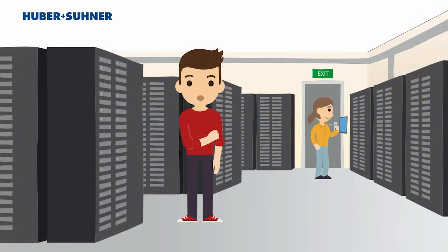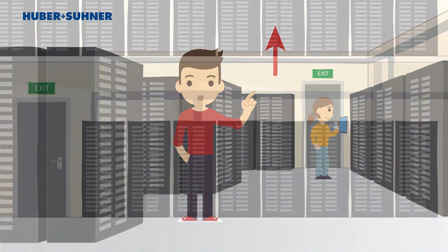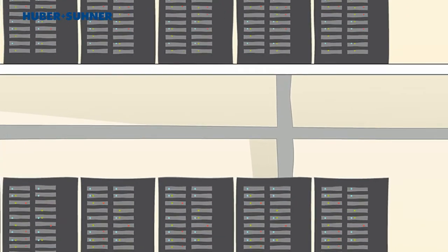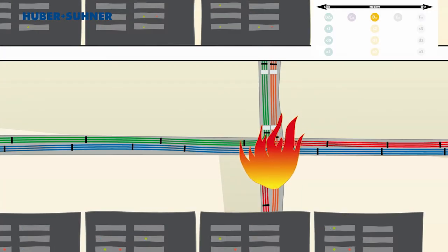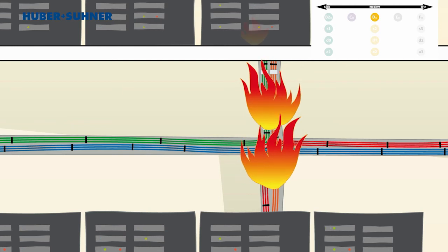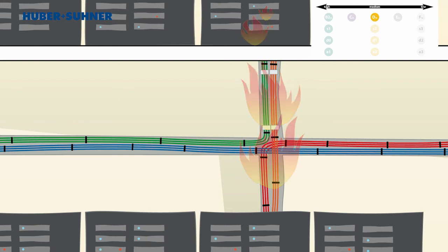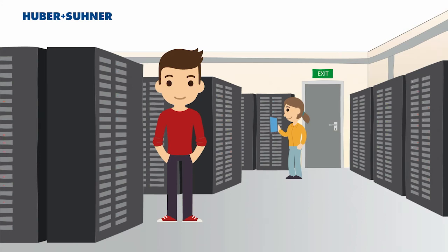Another place a fire might occur is in the cable duct connected to the riser zone. If a DCA cable is installed, the fire would spread throughout the next floor of the data center. With a B2CA cable, the flames would not be able to spread past the riser zone. With such different outcomes, I'm always relieved when I see cables with the highest safety ratings installed.